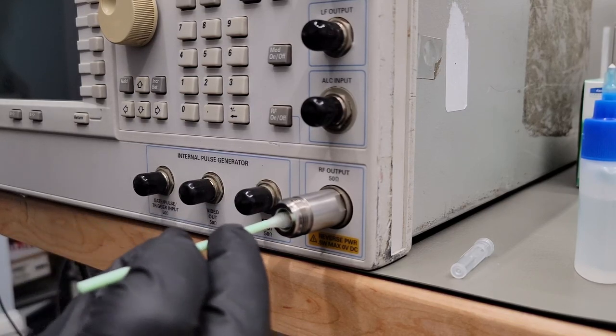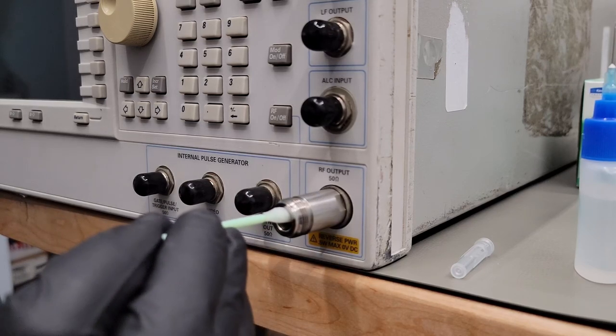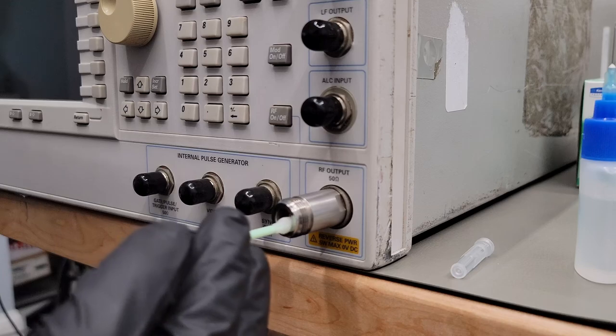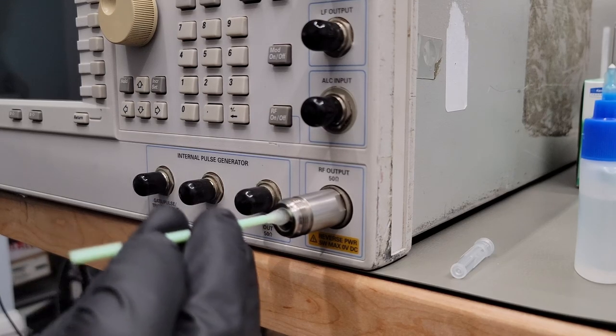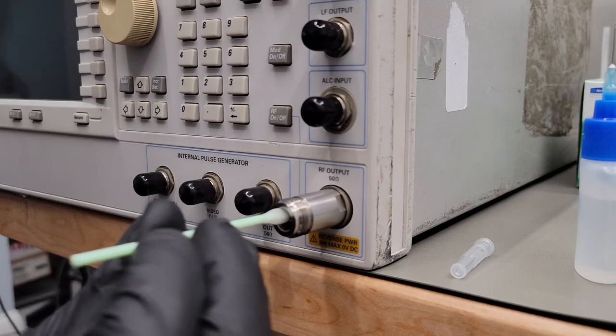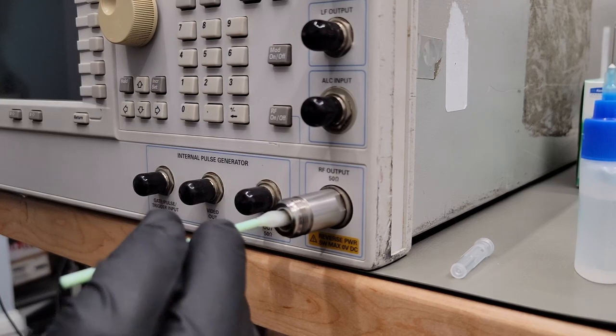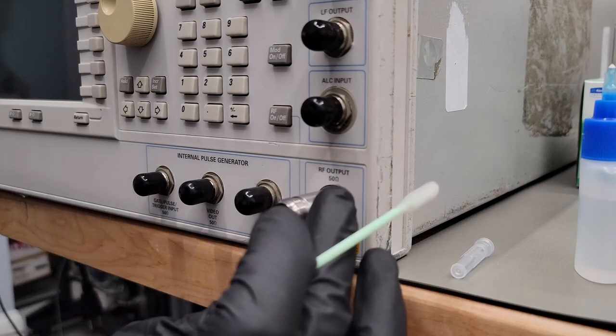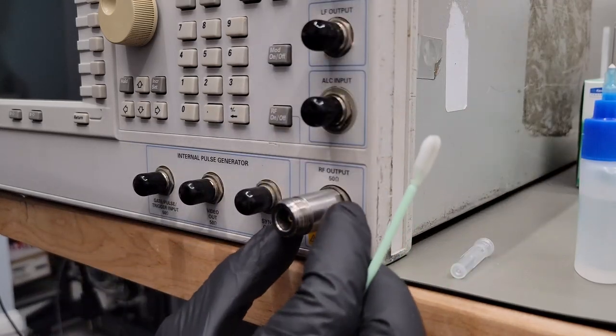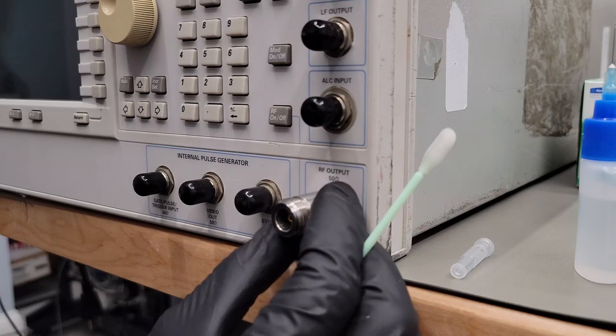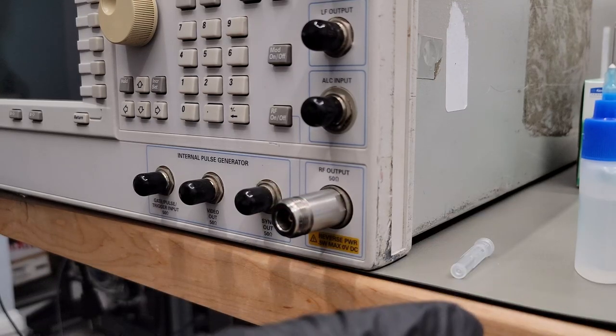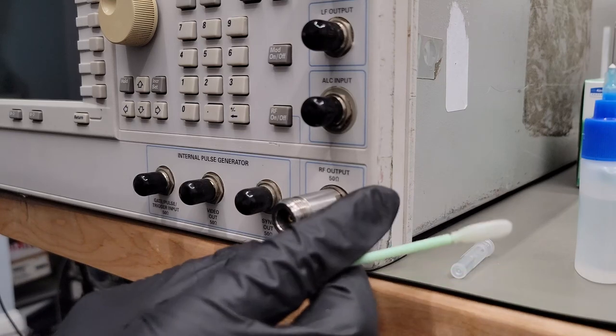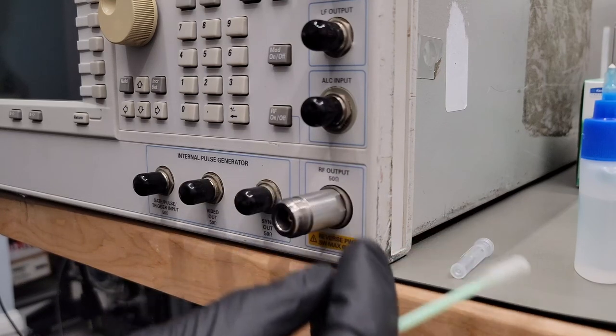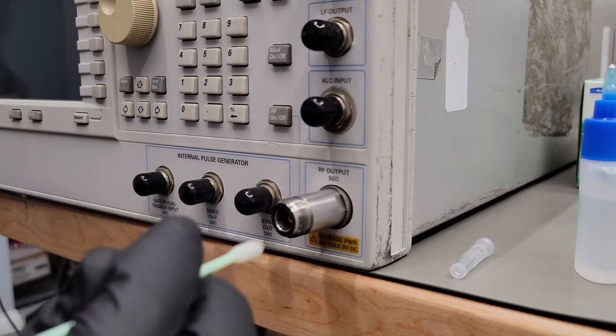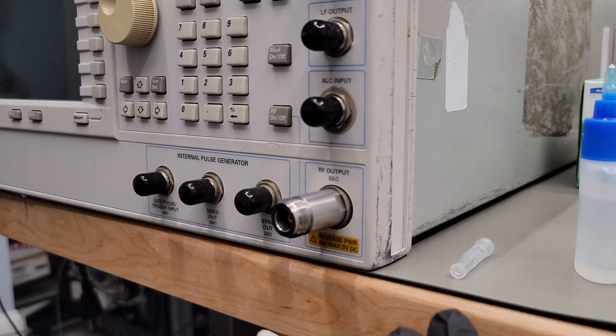One thing to note, this connector specifically is an air dielectric type N connector. So that's done, of course, because you do have better microwave characteristics using an air dielectric as opposed to something like PTFE. But one thing you want to be careful of is in order to make this an air dielectric, there actually is a small suspension framework to hold the center conductor, of course. That's not PTFE, it's another material. Or it could be actually a low reflection plastic. But the bottom line is it's not like the center conductor is encapsulated in a rigid body of PTFE.